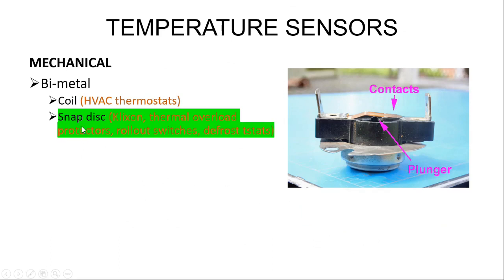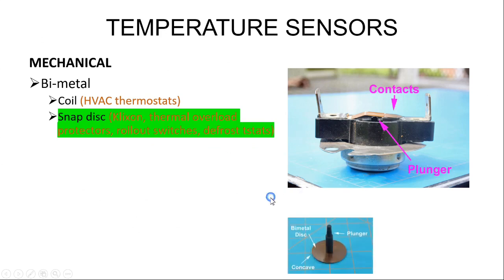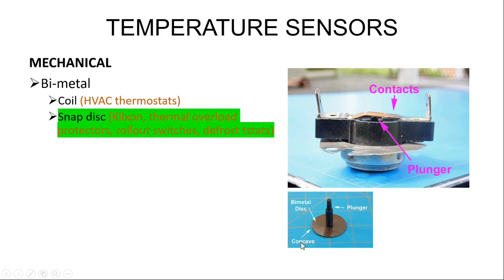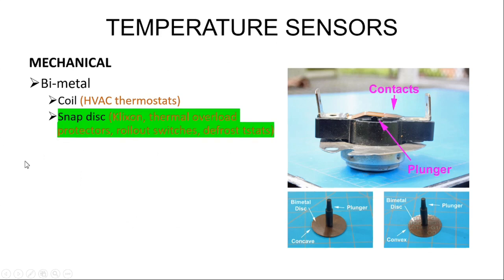This is a very common one, a snap disc, sometimes called a klixon, used as thermal overload protectors, roll-out switches, and defrost thermostats. Now, it has the contacts there, it has a plunger, and down in here, you'll have the actual bimetal disc. In this case, it's showing it as concave, probably a normal state. However, if it gets too hot, then the bimetal disc will snap into a convex state, and the plunger will push up and actuate these contacts to, in this case, open them. The snap disc is not adjustable. It's simply manufactured to function at the temperature at which the manufacturer specifies for the equipment.